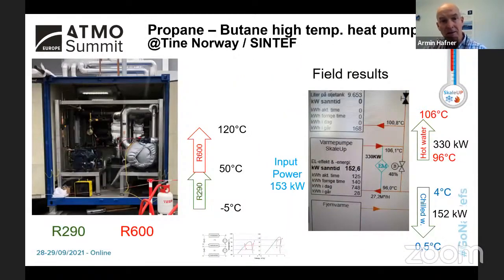We see also propane, butane high temperature heat pumps. This is on the left side, you see an installation introduced in Norway in a dairy where they utilize this two-stage system with the propane in the bottom, producing chilled water with an evaporating temperature of -5. The propane system rejects heat at around 50 degrees, where the butane system picks up the heat and delivers it at 120 degrees C. So this is a relatively high temperature lift, the source at -5, while the hot water which is produced is at up to 120 degrees.